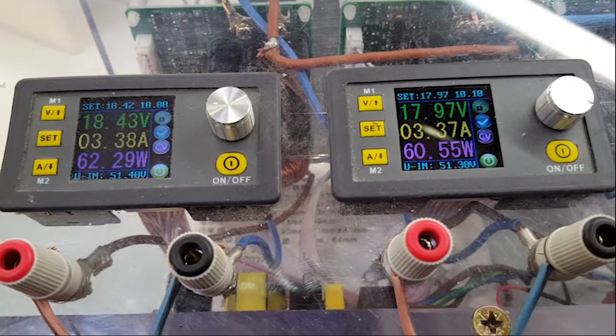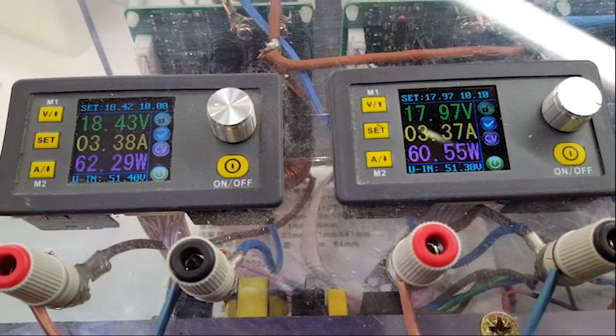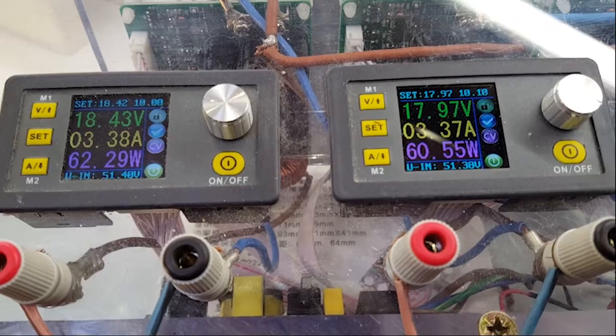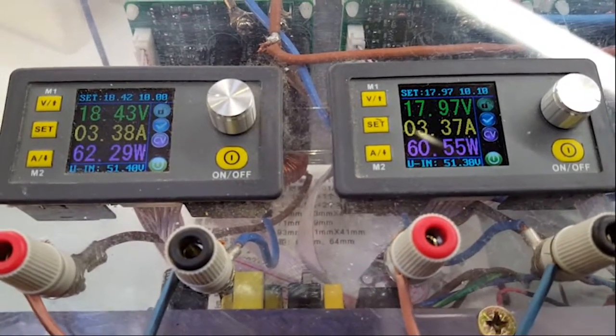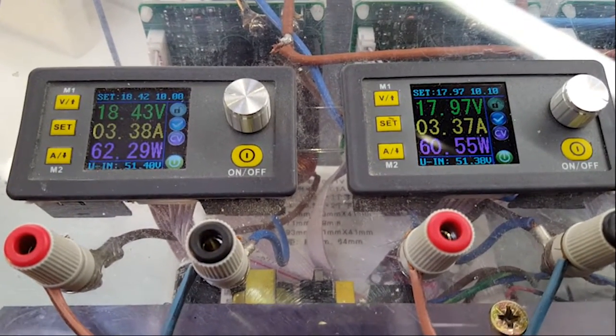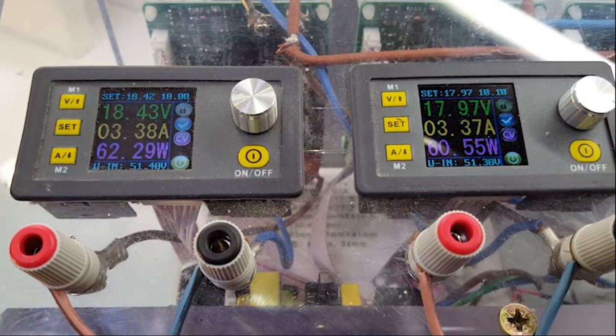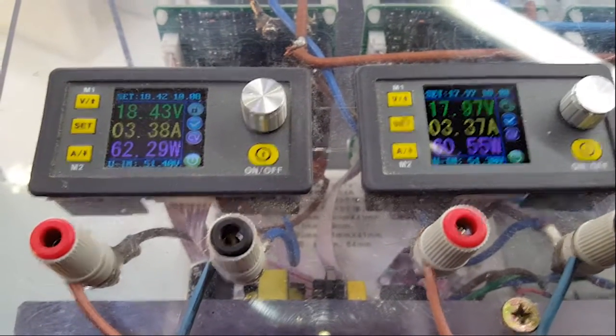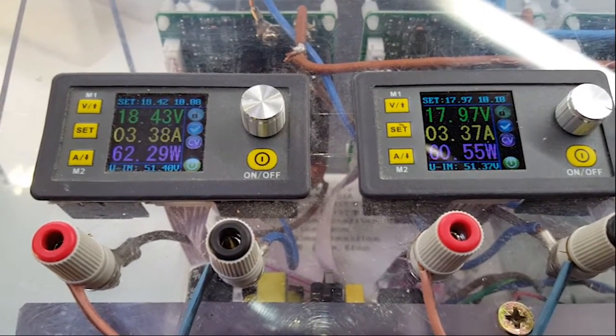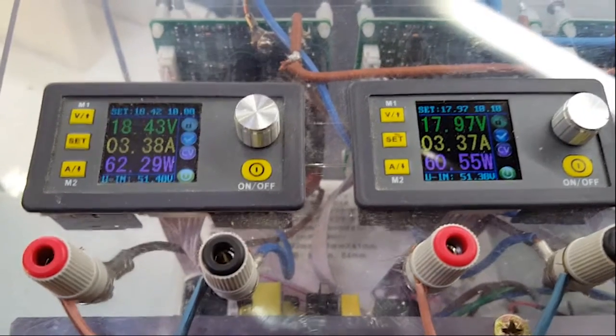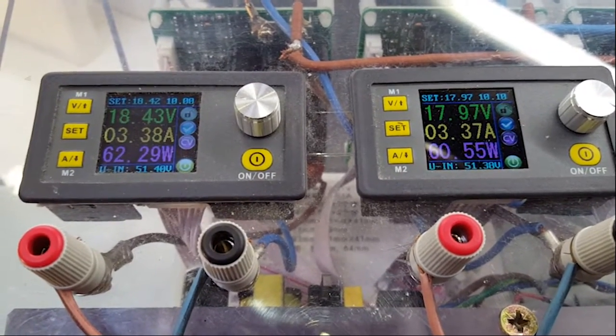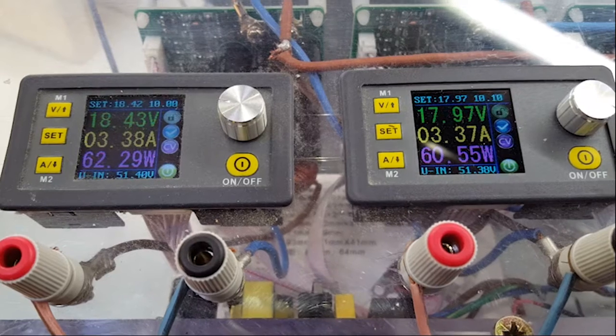This variation is because of very slight differences in the thermal insulation capacity of the reactor materials, the coil disposition, and even the thermocouples. The plan here is to calibrate the entire reactor and plot the current required to keep the tubes at an equal temperature. More on this later.